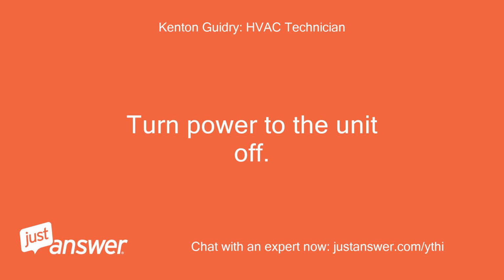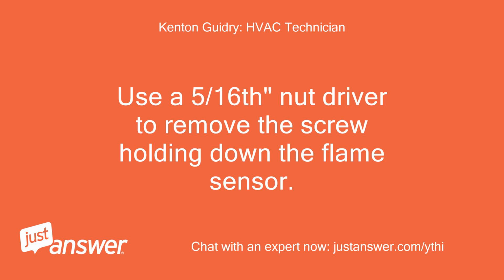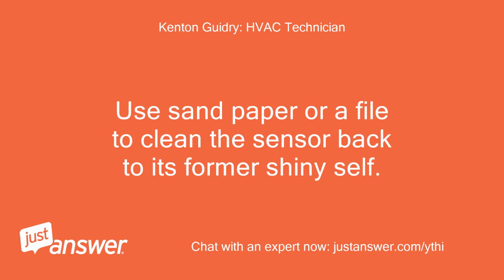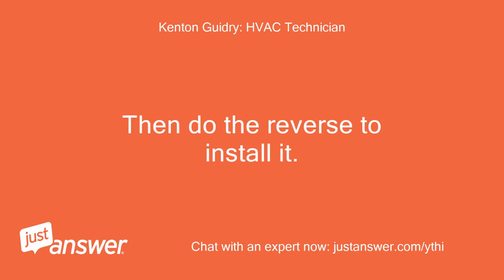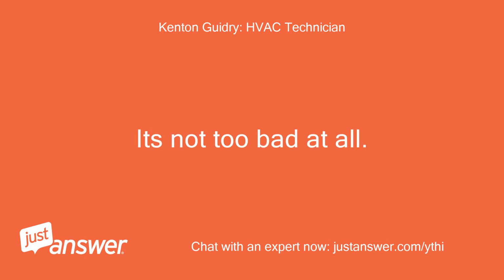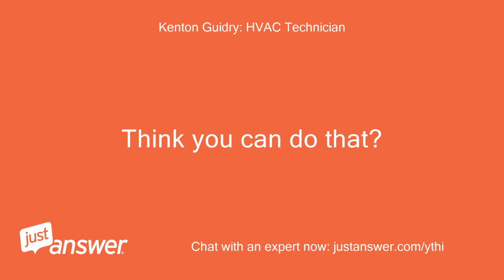Turn power to the unit off. Use a 5/16 nut driver to remove the screw holding down the flame sensor. Use sandpaper or a file to clean the sensor back to its former shiny self. Then do the reverse to install it. It's not too bad at all. Think you can do that?